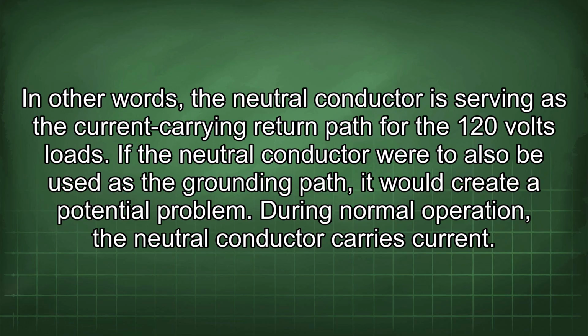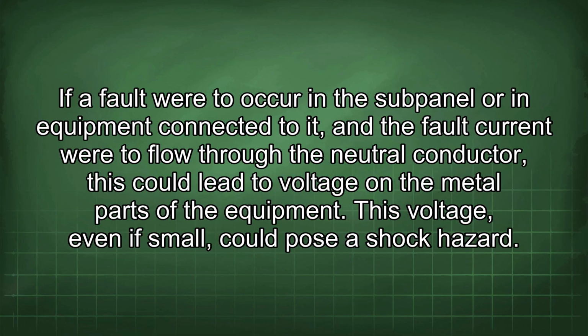In other words, the neutral conductor is serving as the current carrying return path for the 120 volt loads. If the neutral conductor were to also be used as the grounding path, it would create a potential problem. During normal operation, the neutral conductor carries current. If a fault were to occur in the subpanel or in equipment connected to it, and the fault current were to flow through the neutral conductor, this could lead to voltage on the metal parts of the equipment. This voltage, even if small, could pose a shock hazard.